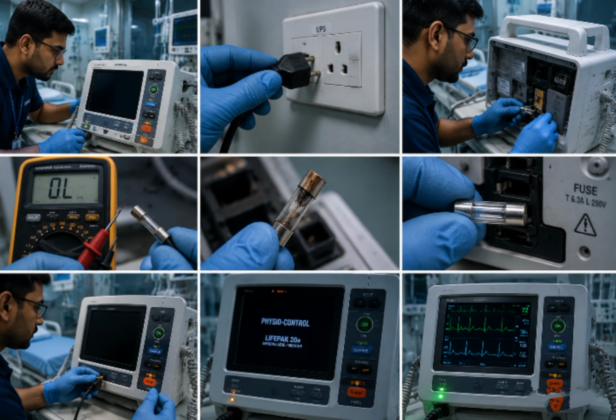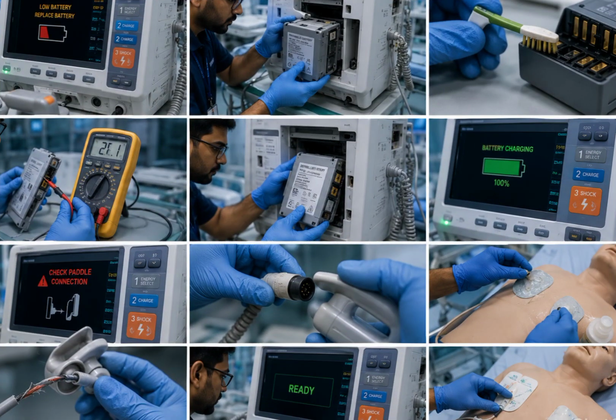If the problem is not in the cable, the second problem which we might face is a battery charging problem. The monitor shows a low battery warning. Remove the battery carefully from the rear compartment. You can see that in an image. Check battery terminals, charging contacts, dust or corrosion. Clean the contacts using a dry lint-free cloth. You can see in that image he is cleaning it with a brush.